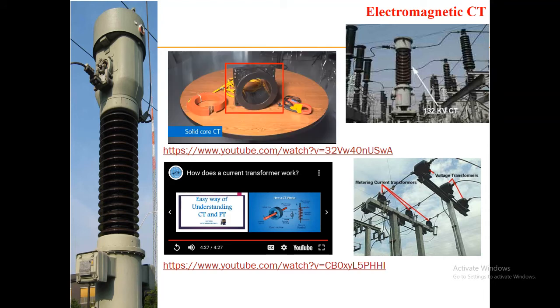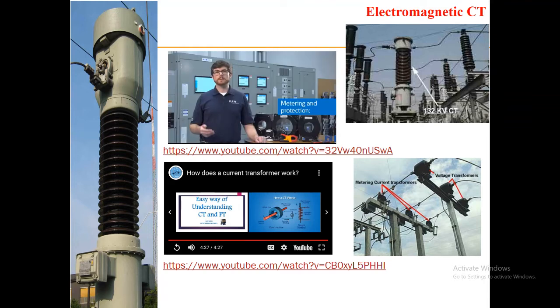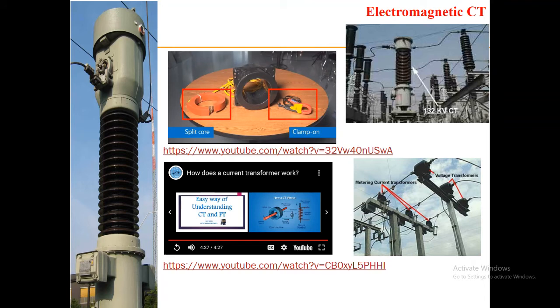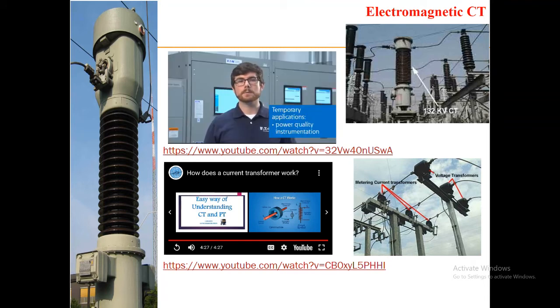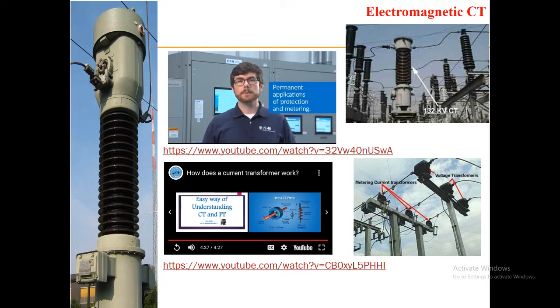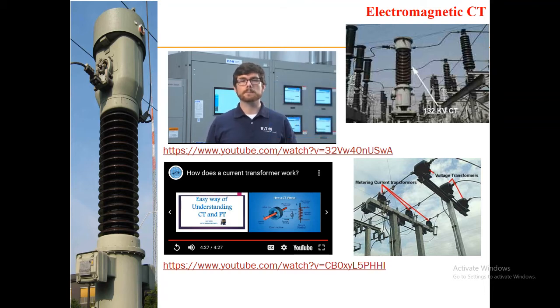Solid core CTs are generally more permanent and are most commonly found for metering and protection in switchboards, panel boards, and switchgear. Split core and clamp-on CTs are generally used in more temporary applications such as power quality instrumentation. For permanent applications of protection and metering, CTs can be found anywhere from generators to transformers to connected loads, or anywhere we want to monitor current flowing in the system.